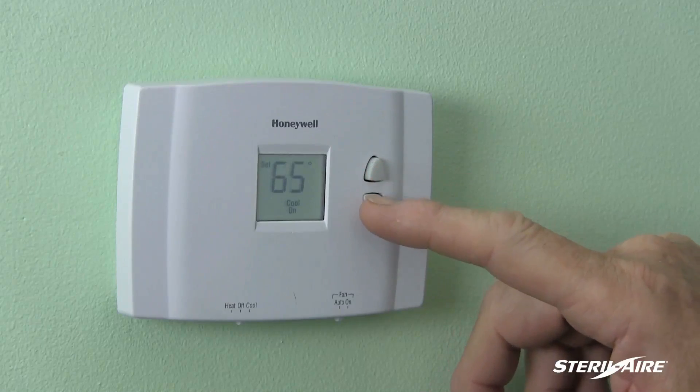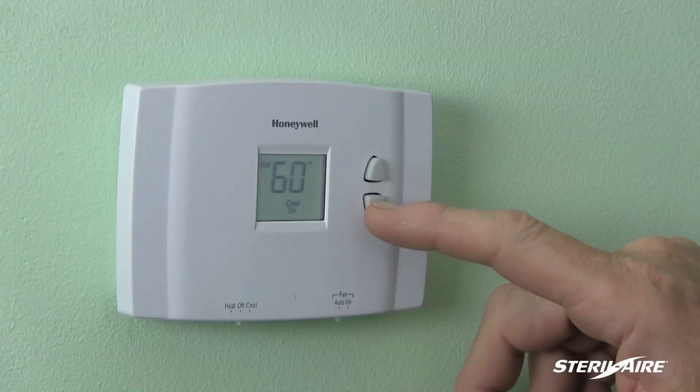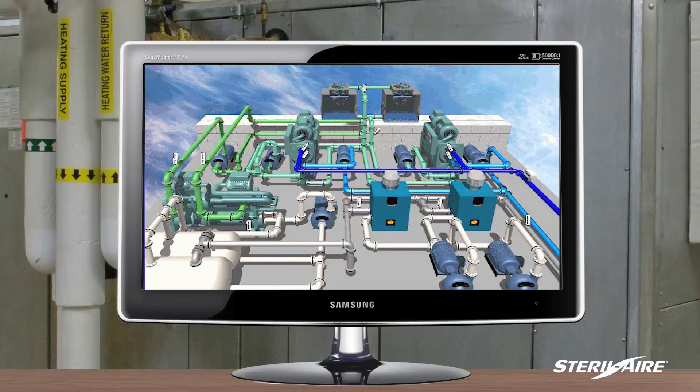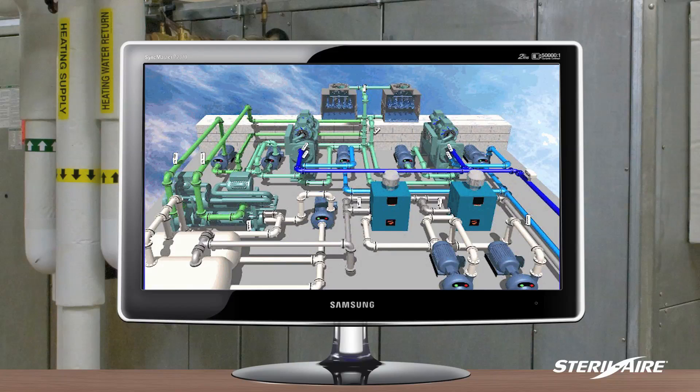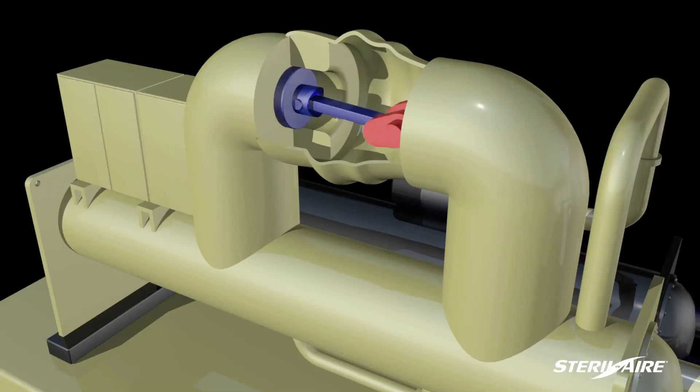To achieve the desired thermal comfort, either the occupants alter the thermostats, or the maintenance department adjusts the chiller set point. In either case, this increases the electrical consumption of the chiller and pumps.